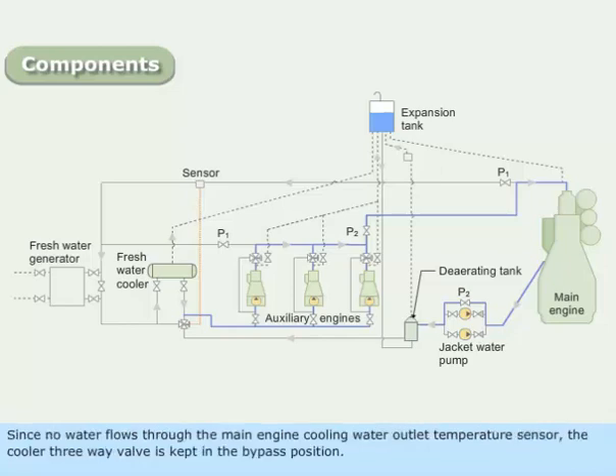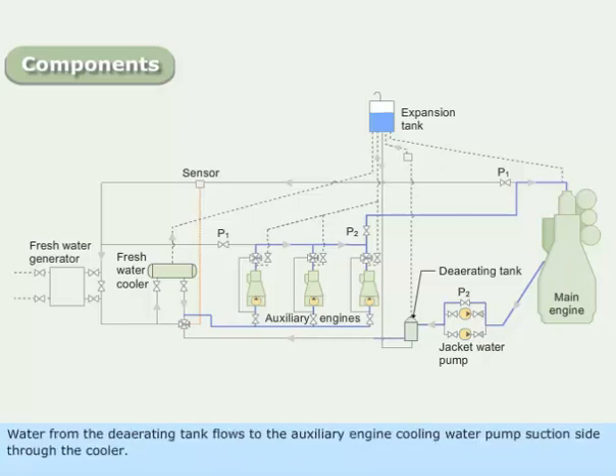Since no water flows through the main engine cooling water outlet temperature sensor, the cooler three-way valve is kept in the bypass position. Water from the de-aerating tank flows to the auxiliary engine cooling water pump suction side through the cooler.